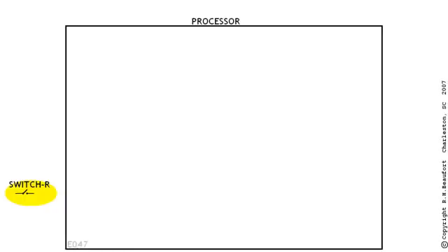Suppose that we have a real physical device named switch R wired up in the field. We'll keep things simple by not showing the wiring, but it's there. Now consider that we've also got a bit, a box, named switch R located inside the processor. And we've also got an instruction addressed as switch R inside the processor as part of the PLC's ladder program. So, like it or not, that gives us 3 separate things, and each one is called switch R.